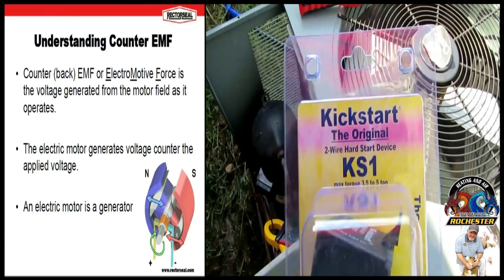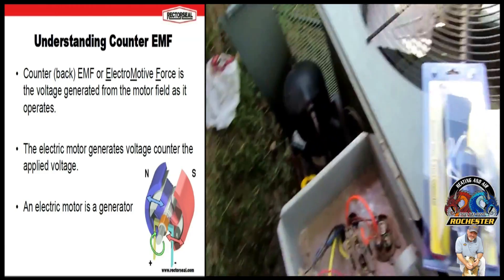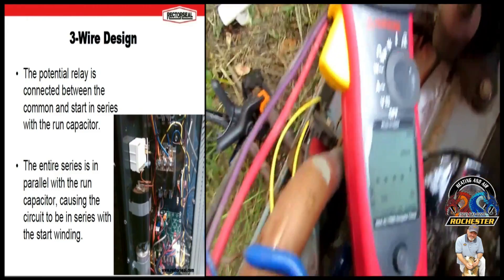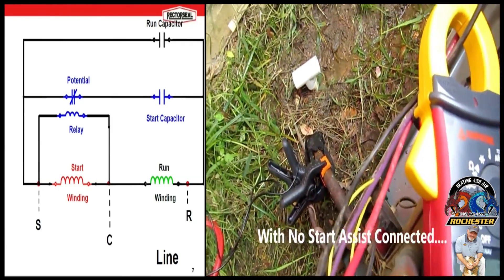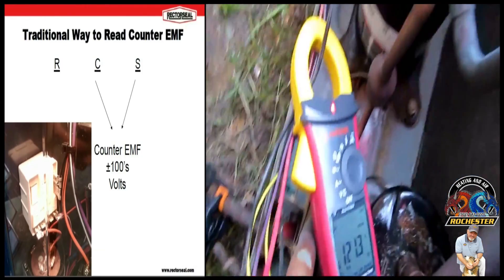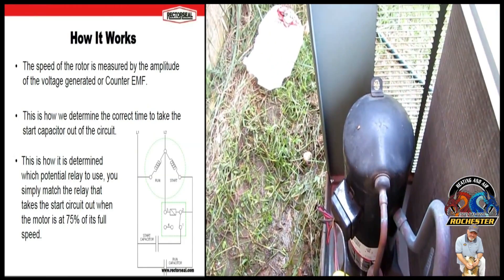Hey guys, I'm going to install the Kickstart KS-1 on this 4-ton Rheem heat pump. But first I'm going to show you what the inrush is without it. Get the camera over here and I'm going to amp the unit for you. Got it on the common wire to the compressor there. 121.3 guys. Let me get this installed and we'll see what the difference is.